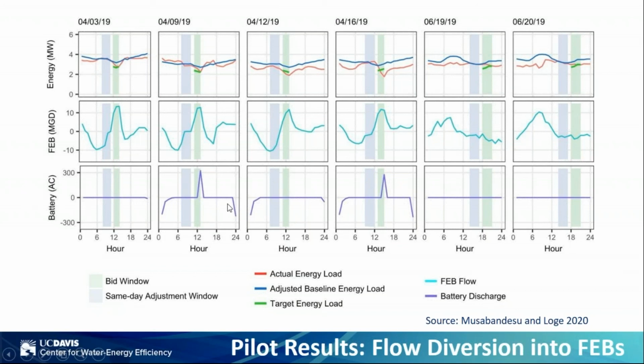And for these test events, a couple of the test events also included discharging the battery. In these final 2 test events here, you can see that the operators, I think, were trying to help with some of the delays in energy, and the timing just was completely off. So there obviously are some issues between trying to get the timing to work, also some issues in properly measuring the energy reduction.